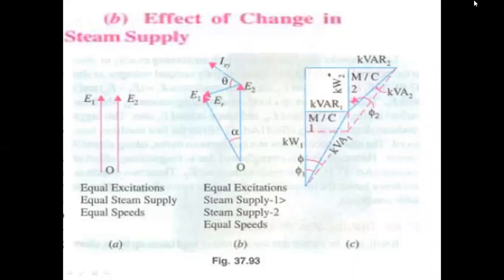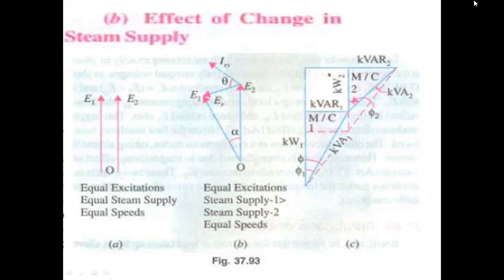Because the machines are tied together, even though we increase the steam supply to the first alternator, it cannot run with more speed than the second alternator. However, it will utilize the increased power input for carrying more load than alternator two — that is the only advantage.